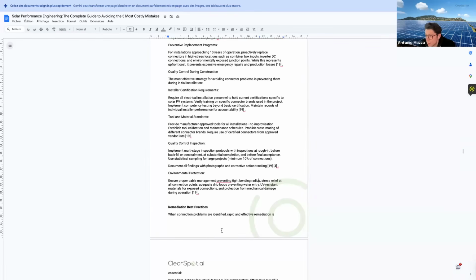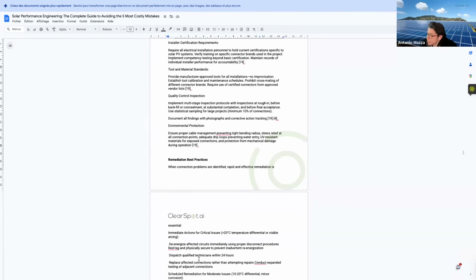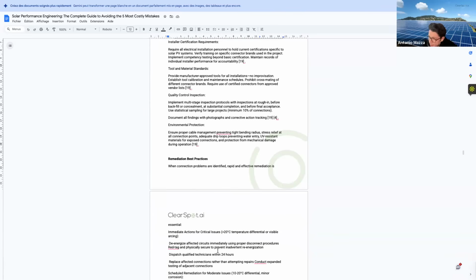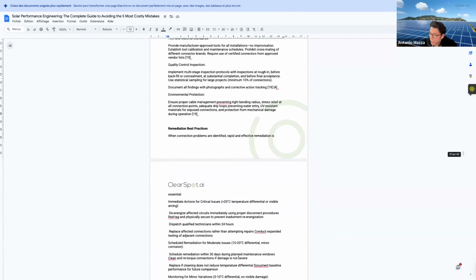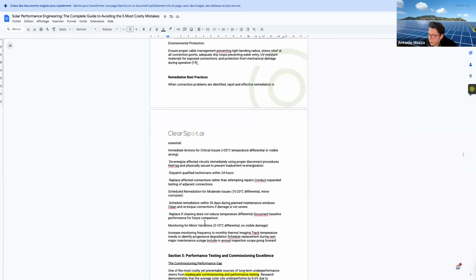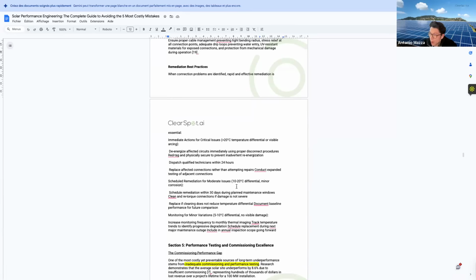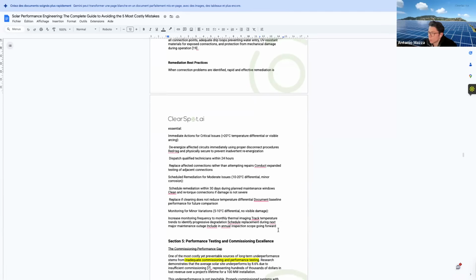Remediation best practice. When connection problems are identified, rapid and effective remediation is essential. What to do? Immediate action for a critical issue, over 20 Celsius temperature differential or visible arcing: de-energize affected circuits immediately using proper disconnect procedures, and dispatch a qualified technician within 24 hours. Schedule remediation for a moderate issue, between 10 and 20 Celsius differential, within 30 days. For a 5 to 10 Celsius differential with no visible damage, increase monitoring frequency with more thermal imaging and track temperature trends, identifying progressive degradation. Schedule replacement during the next major maintenance outage and include it in the annual inspection scope going forward.